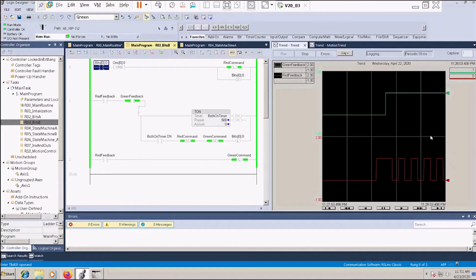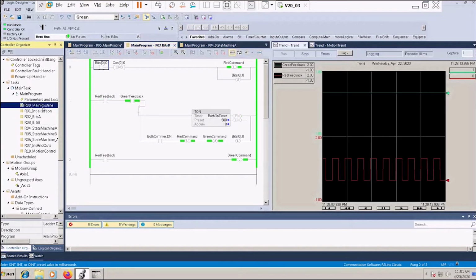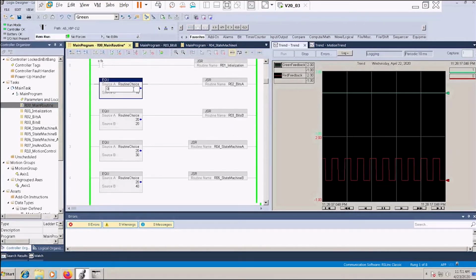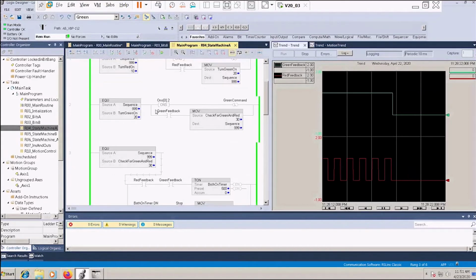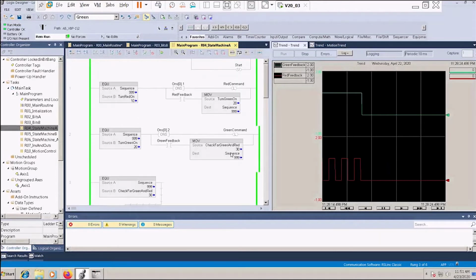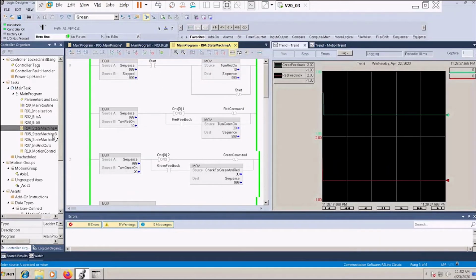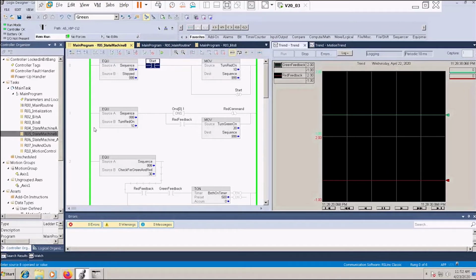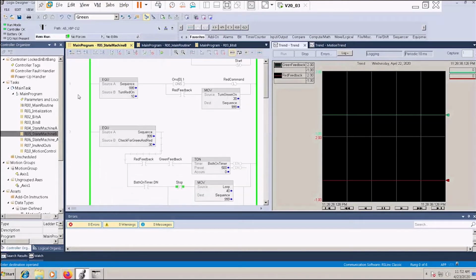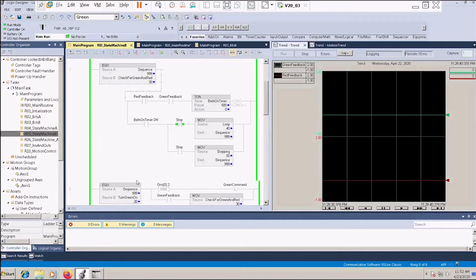Oh, wait, we've got some funky pulse widths. This is not the correct operation. My green is staying on, and I'm doing a faster trigger on my red. The machine is not working. Well, let's stop all that madness. Remember state machine A: green command, red command, then this order of operations with the timer. State machine B is an exact replica, except I have the red command, then the timer, then the green command. Order of operations differs, yet the same state checks.